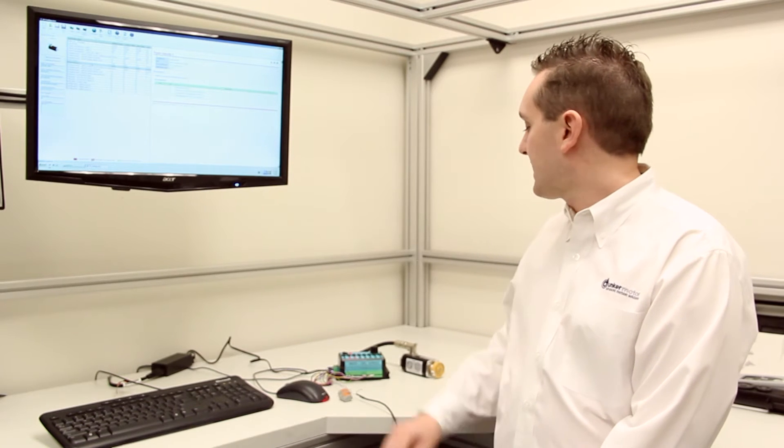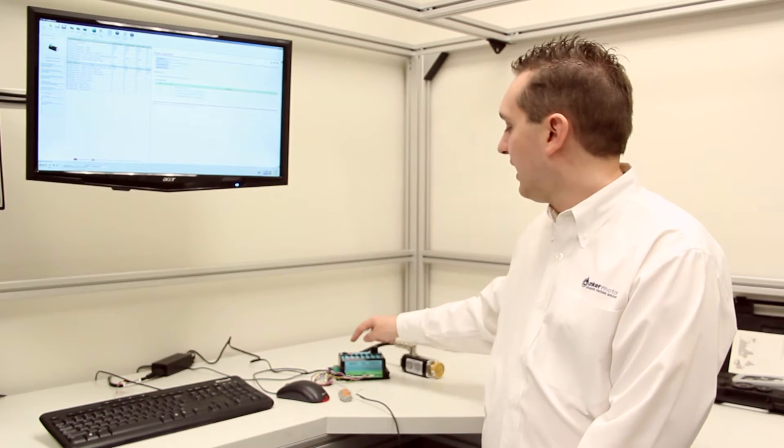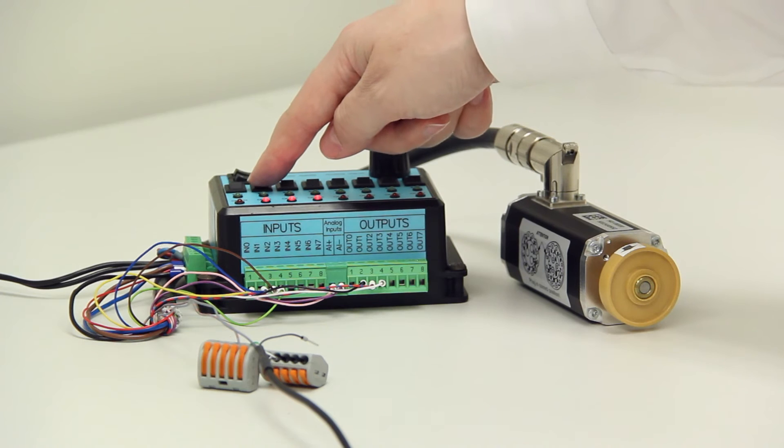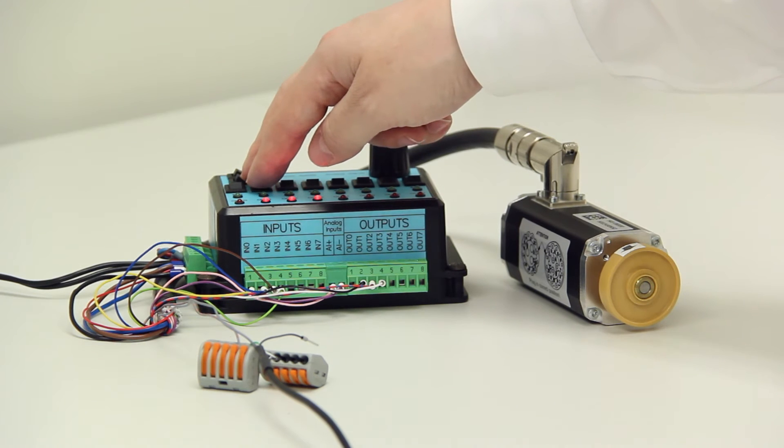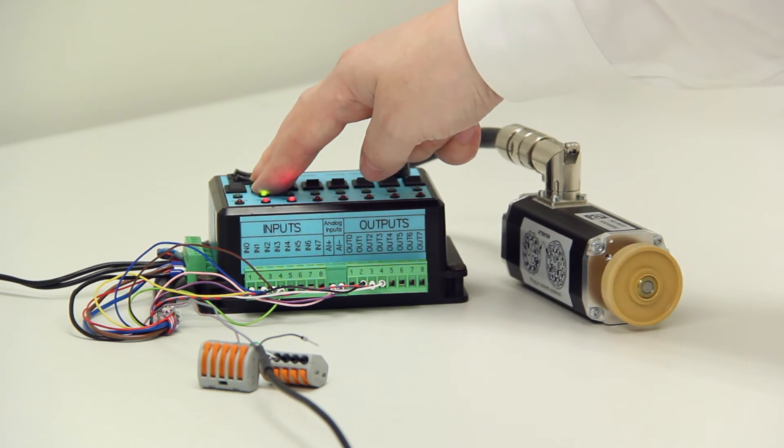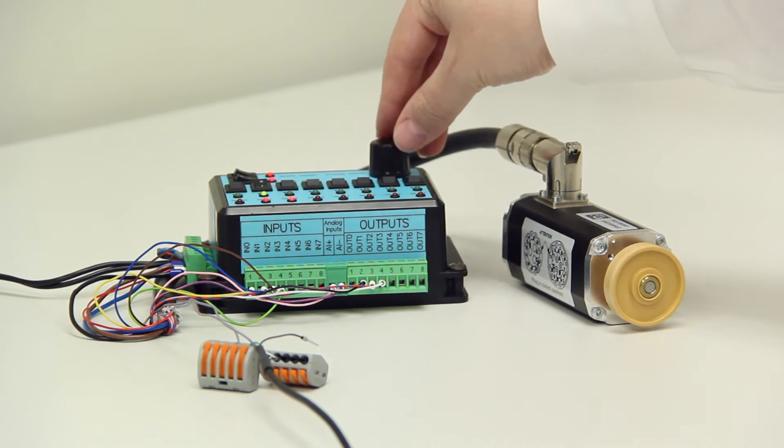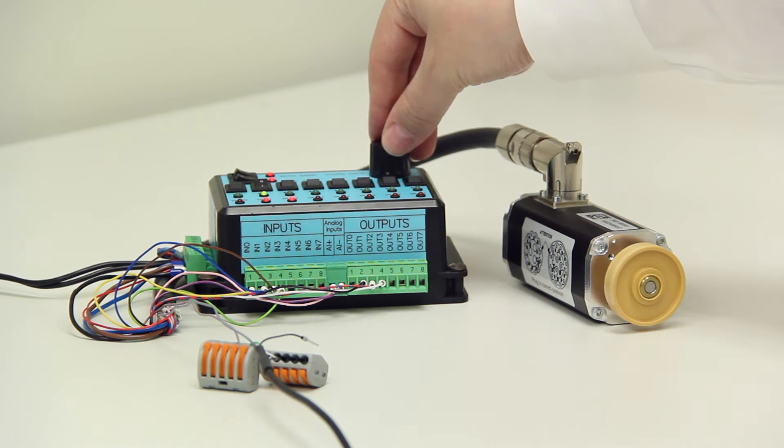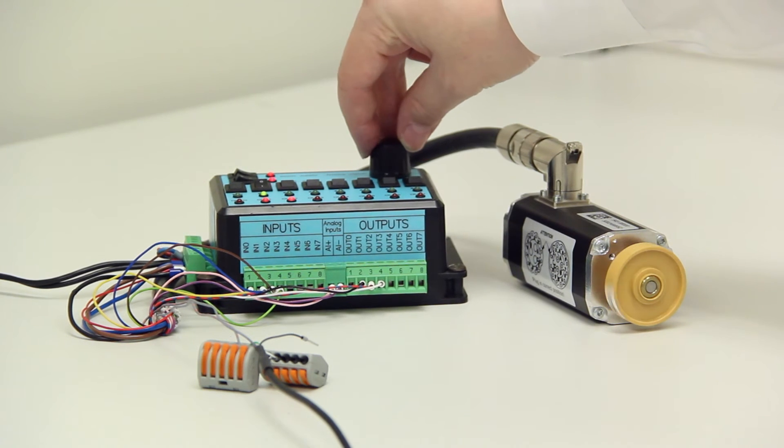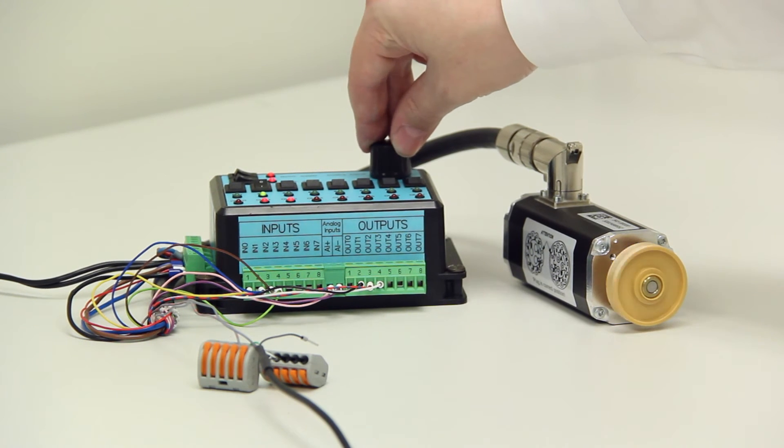At the moment the motor is set to its default settings. If I select a direction by using input 0 or input 1, the motor will rotate depending on the voltage that's applied to the analog voltage stick here. The analog voltage is a range between 0 and 10 volts.